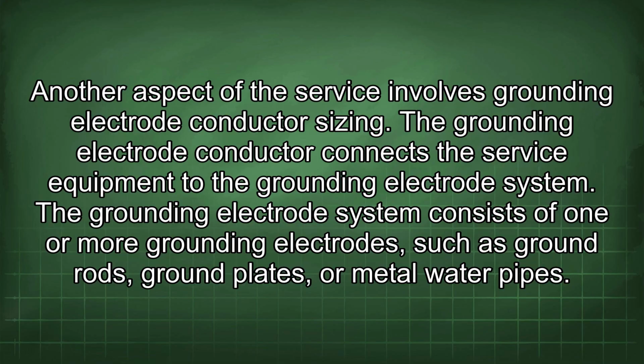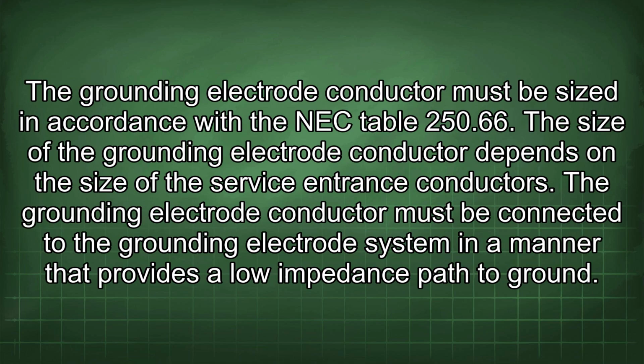The grounding electrode conductor connects the service equipment to the grounding electrode system. The grounding electrode system consists of one or more grounding electrodes, such as ground rods, ground plates, or metal water pipes. The grounding electrode conductor must be sized in accordance with NEC Table 250.66. The size of the grounding electrode conductor depends on the size of the service entrance conductors.